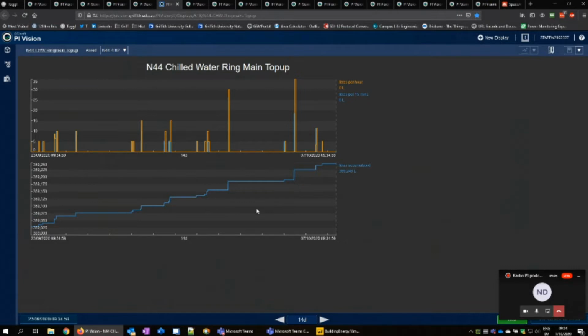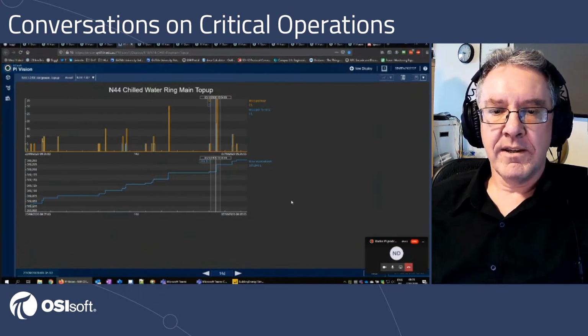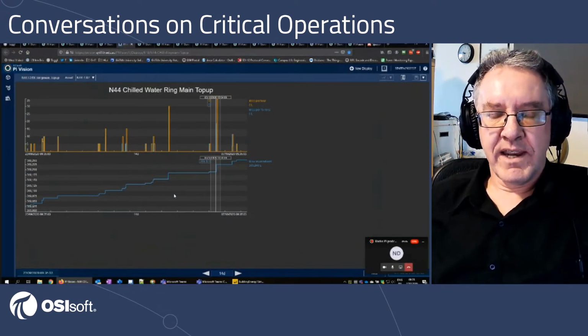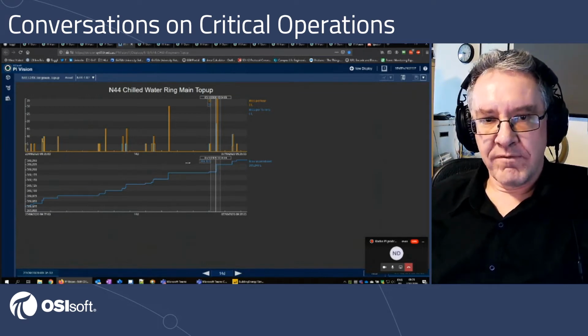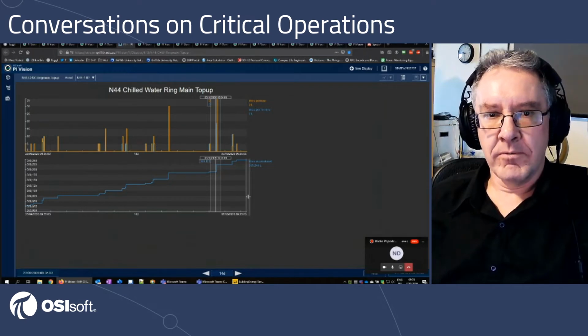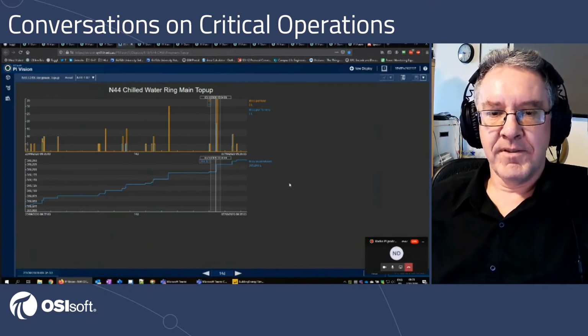Again, looking at management, this is a water meter that looks at the chill water ring main at our main campus. You can see occasionally we're seeing a little bit of water going into that ring main. If that starts to ramp really fast, we'd start looking for leaks in air handling units, walking around the campus looking for green water running down a drain somewhere, which says we're pumping lots of water into the ring main. Now you expect a little top up here and there, there's going to be the odd leak. But again, simple checks, trying to look at the right levels from a condition-based maintenance perspective. This will then email the hydraulics engineer and the mechanical guys to say, hey, you've got a chill water problem, go looking.